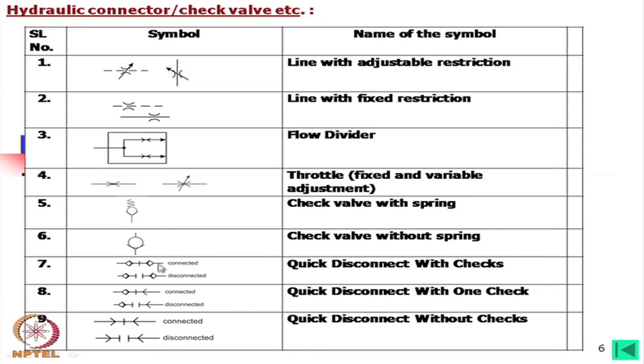In one configuration, only one side has a check valve and the other has no check valve. There is also a quick disconnect without check valves. Depending on the purpose these are used. When a quick connector with check valves is used in a line, oil from one side cannot move to the other side and vice versa. These valves can be pilot-operated externally so that in normal condition they act as check valves, but if a pilot signal is sent, they will connect.